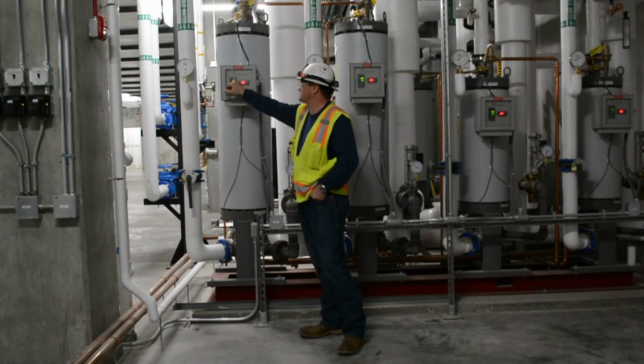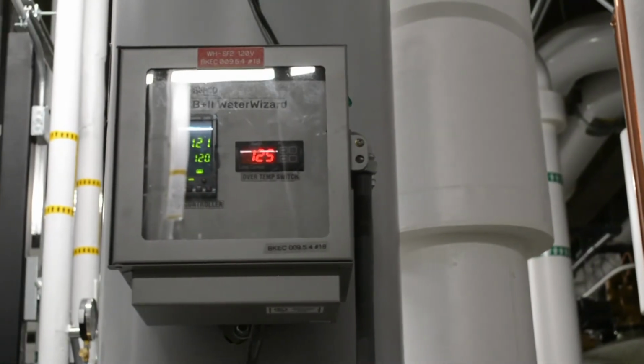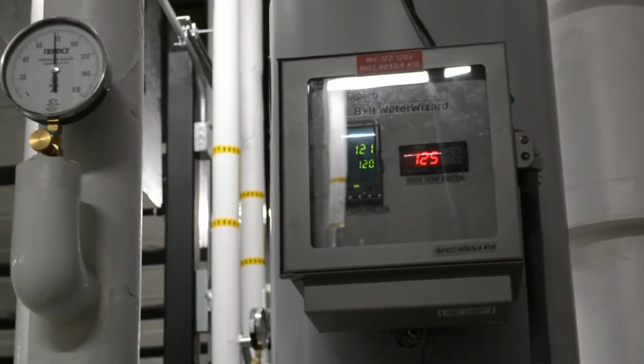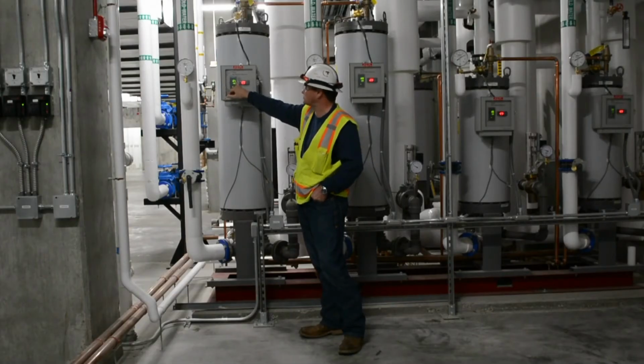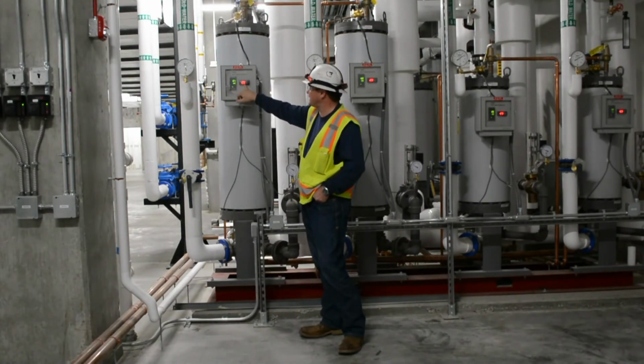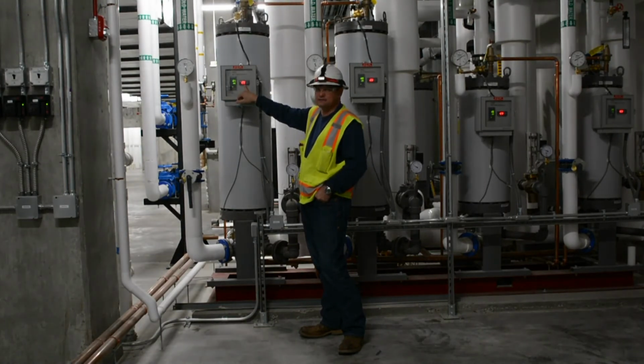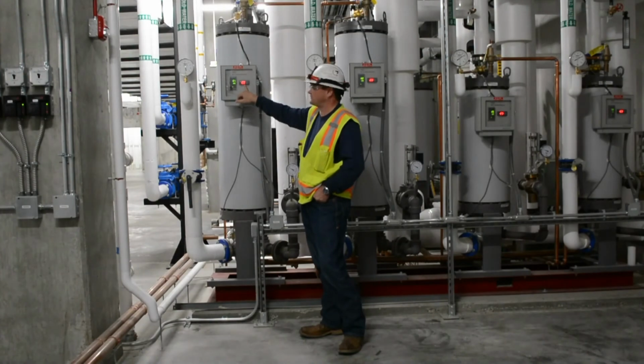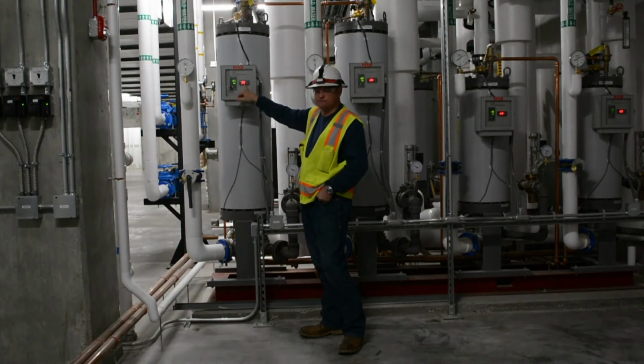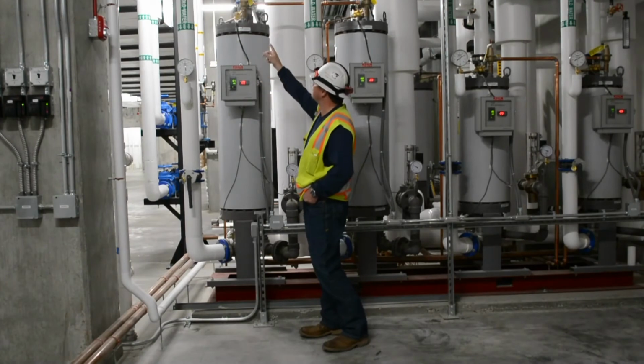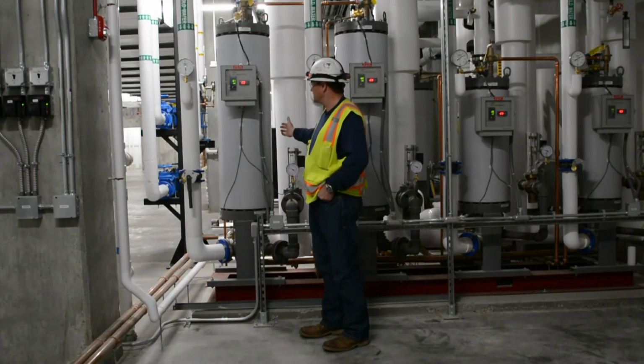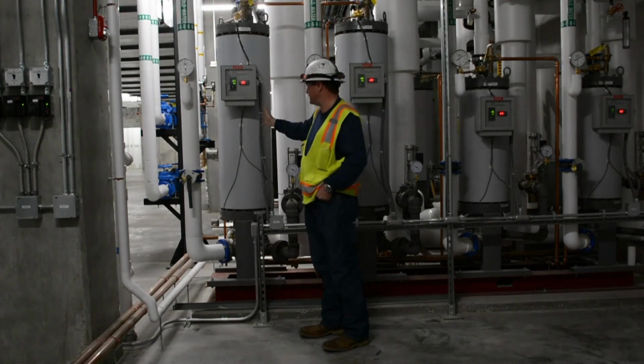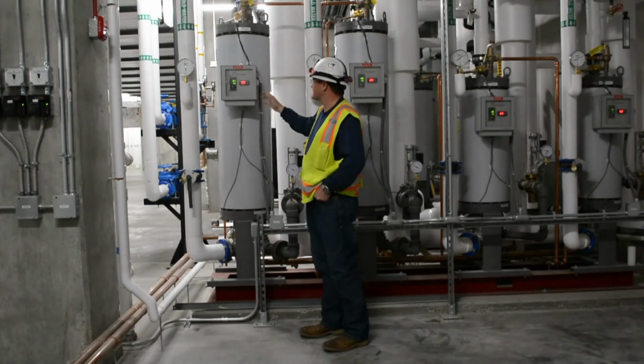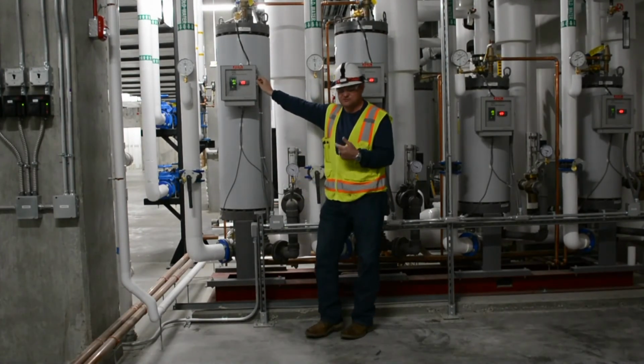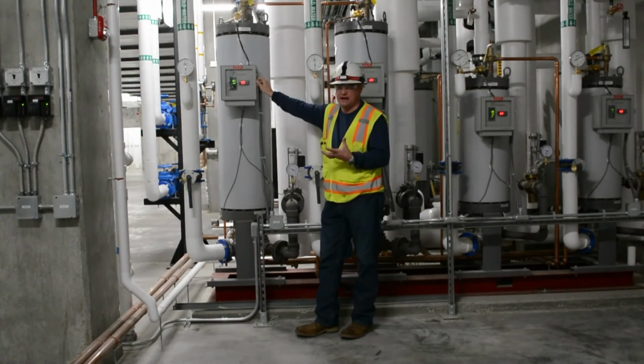The main PID controller is located here. You can see the set point. It's set to 120. The actual temperature is right above that at 121 F. This item here is the alarm high limit. What it does is if the water temperature gets too high, say 140 degrees, it will open up a valve on top in order to blow down the boiler and make sure that it's not overheating. I highly recommend that whenever you do service on these, which you'll do annually, you want to blow them down, check for sediment, things of that magnitude.